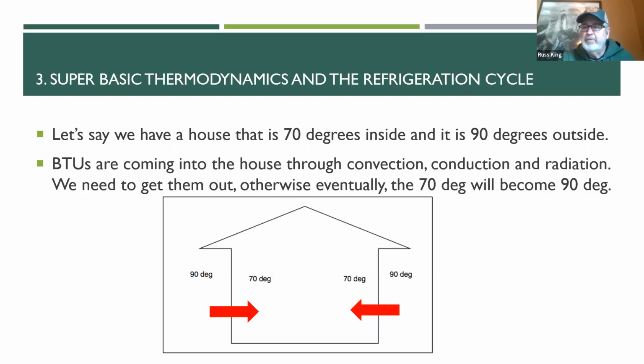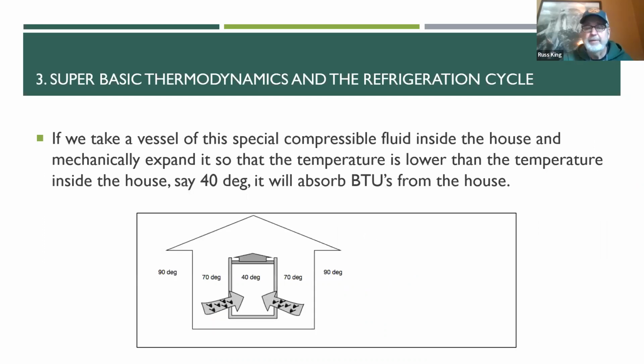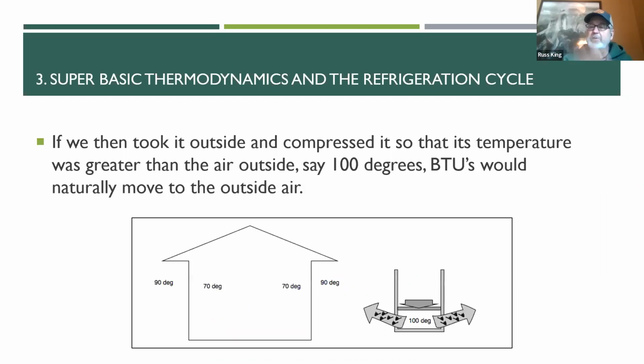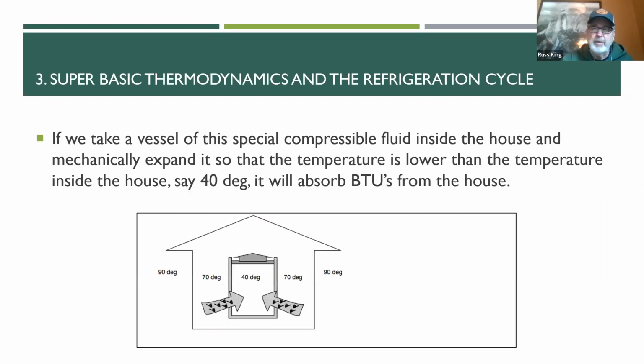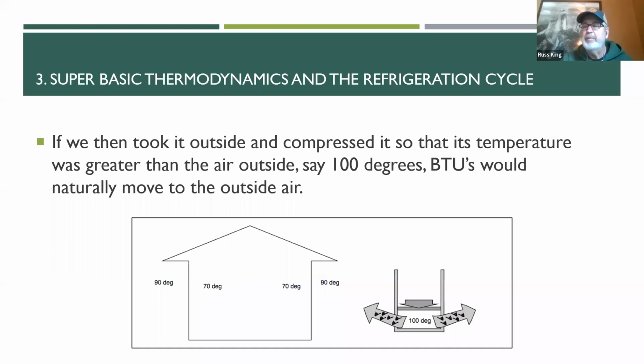So let's say we have a house, it's 70 degrees inside the house and it's 90 degrees outside. The BTUs are naturally coming into the house because it's warmer outside, and the second law of thermodynamics says heat travels from warmer to colder, so heat is coming into the house. If we let that continue, eventually the house is going to become 90 degrees, but we want to keep it at 70 degrees. So we take our little container and bring it inside the house and expand it until the temperature inside the container is 40, and we absorb some BTUs. Then we take it outside and squeeze it, and dump the BTUs to the outside. If we just keep doing that, absorb, squeeze it out, absorb, squeeze it out, we can actually pump BTUs out of the house. And if we can do that at the same rate that they're coming in, we can maintain a constant temperature inside the house.